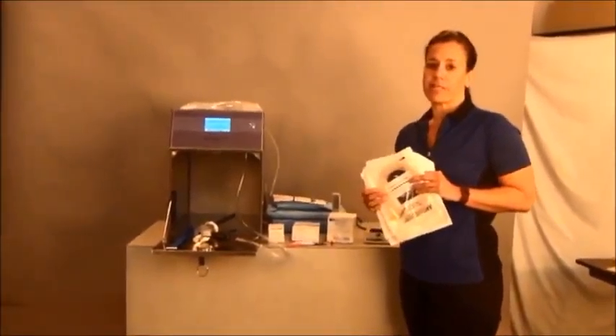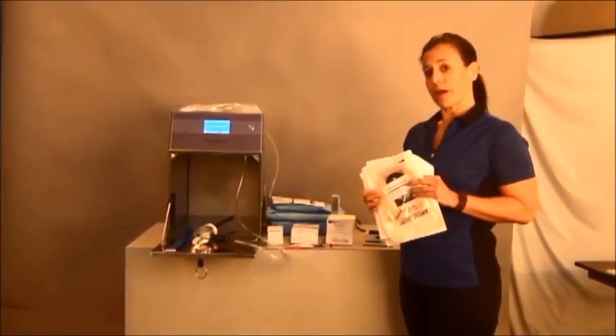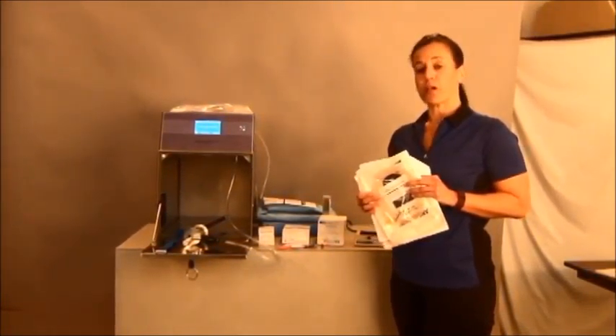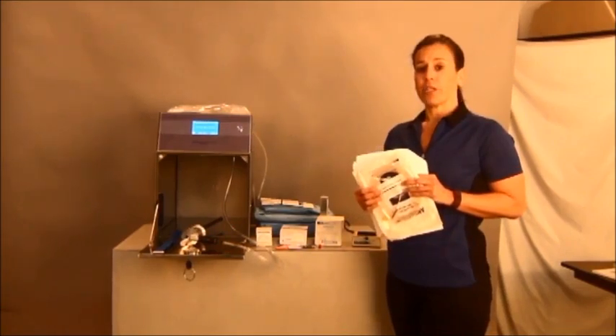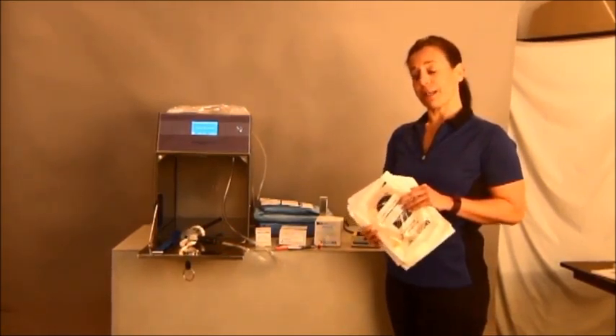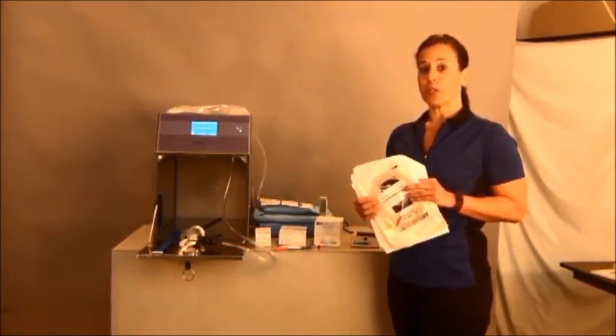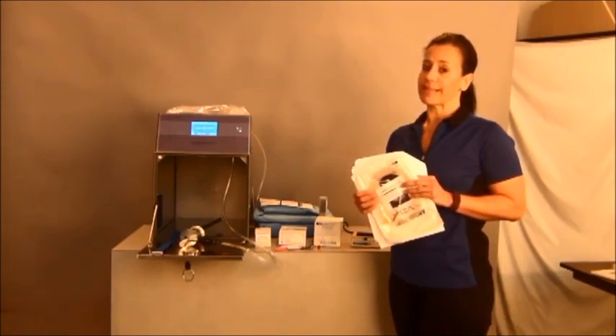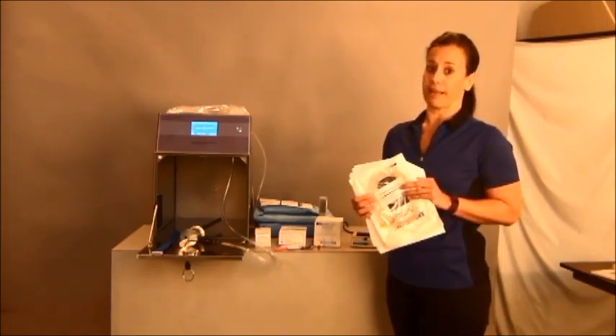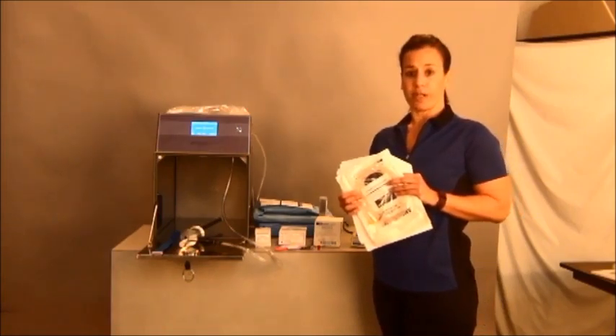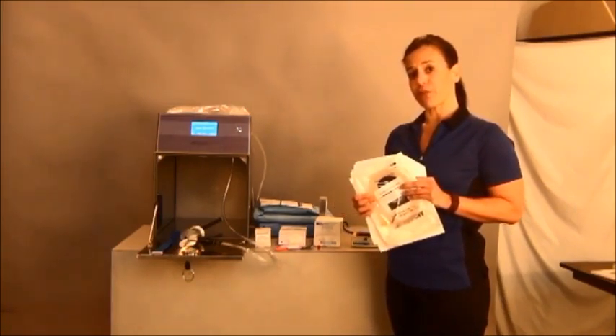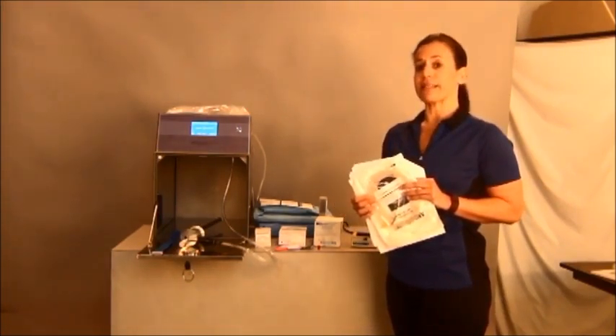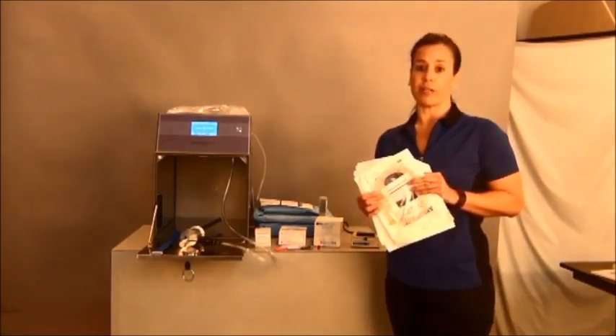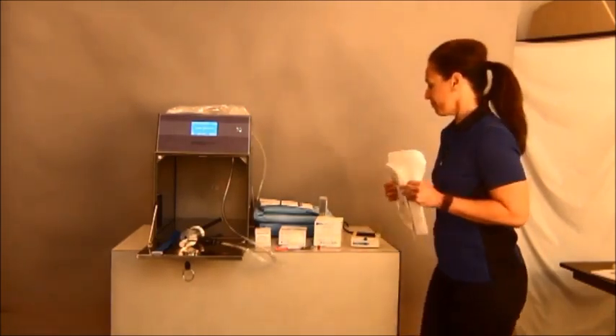The drying of the items can be done by towel drying, air drying. You can also use compressed air. You want to avoid heat to dry any of your items, as it could make bacteria spores desiccated and resistant to ethylene oxide. Again, you want to make sure that you meet the AAMI standards for humidity, which are at least 30% in the area in which the items are prepared.